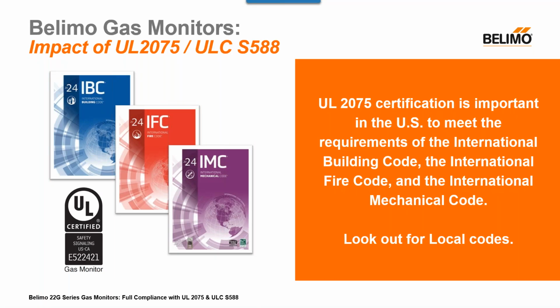Ensuring safety and compliance: meeting UL standards ensures alignment with building codes and industry regulations, minimizing liability for building owners. The International Building Code requires that buildings use UL 2075 listed CO monitors, detectors, and sensors. The International Mechanical Code mandates that all CO and NO2 monitors, detectors, and sensors in enclosed parking structures must be UL 2075 listed. In addition, the International Fire Code specifically states that CO detectors shall be listed in accordance with UL 2075.